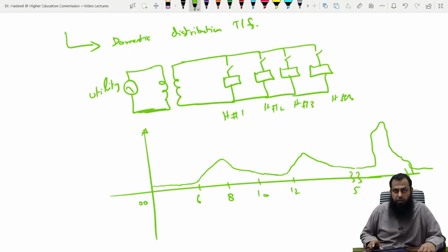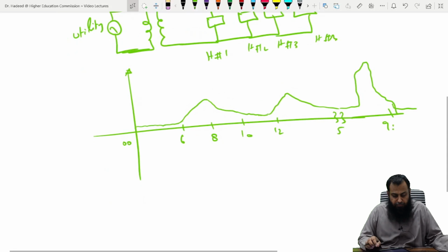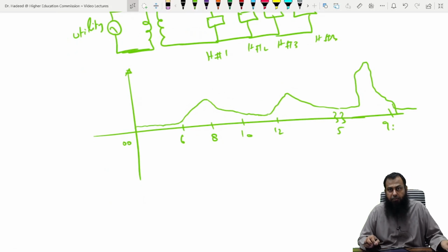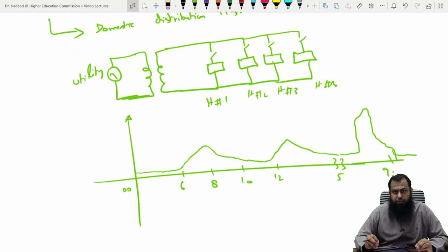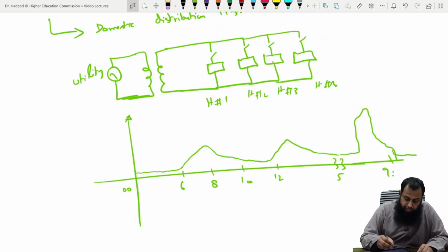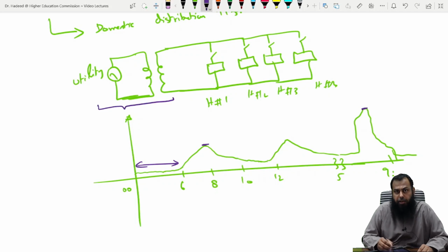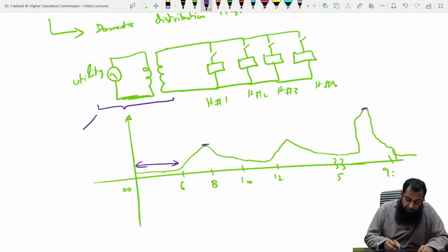So for these types of applications where the transformer is not connected with a fixed load, there are two things that we need to understand. The first thing is, even if this transformer is working with this load, or with this peak, it always draws some current to ensure the magnetization happening inside the transformer core, and therefore for all kinds of loads, the core losses are there.